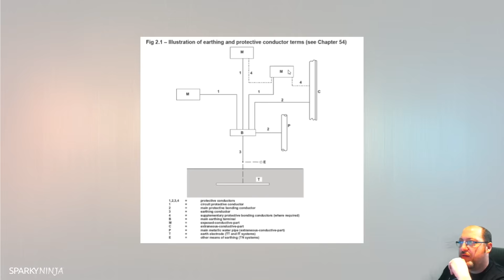Now M are exposed conductive parts - this could be a cooker, a boiler, whatever. You notice the circuit from the main earthing terminal to the exposed conductive parts is simply the CPC, the circuit protective conductor. However, between exposed and exposed conductive parts - boiler to cooker - or exposed to extraneous conductive parts - boiler to steelwork - there could be this other conductor labelled 4, which is your supplementary bonding.